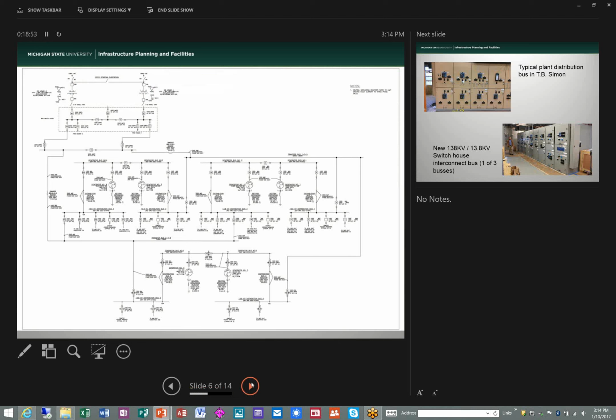This last week the plant was cruising at about 67% efficiency—we're making money, good time of year, sending out steam with low electric demands. We're probably making 40% efficiency in the summertime with historic practices, where we've got 60 megawatts and we're making 30 megawatts with our send out to campus. But the rest we could make as condensed power cheaper than buying it on the grid.